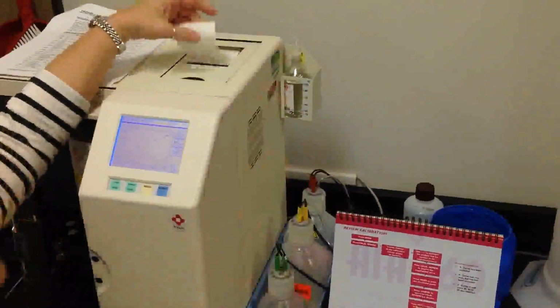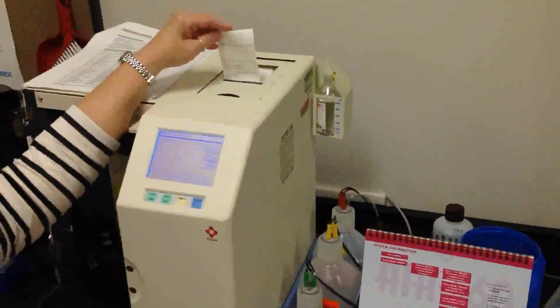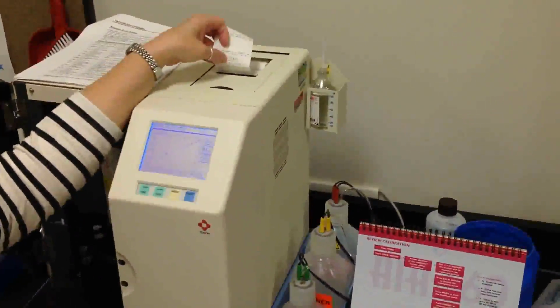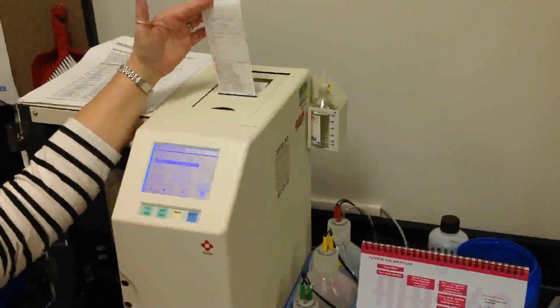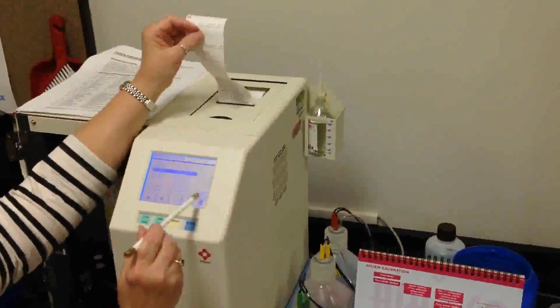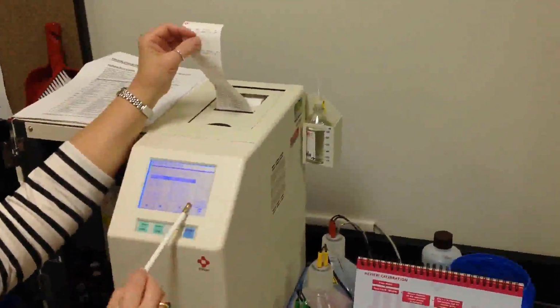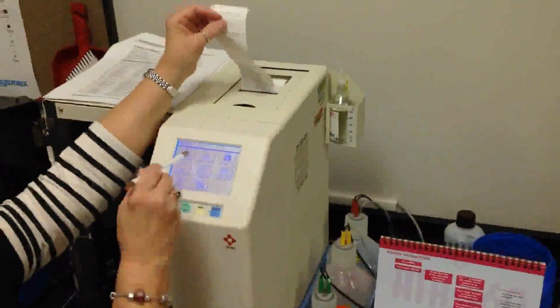It prints out all your data along with your graph with status of accept. And that P will now be an A for accept. So let's just go back to Calibrate Review. And here it is. Now it has an A because it's been accepted. I want to exit.